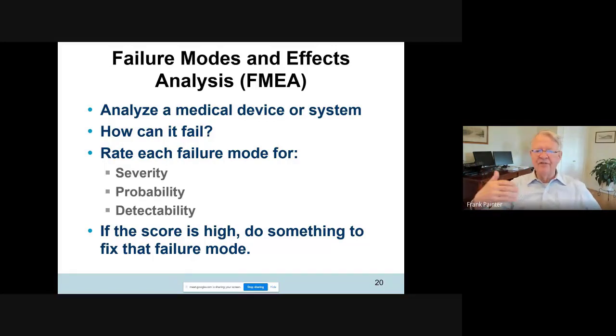So what we're going to do is have the nurses do a little check on the defibrillator every day, and they're going to plug it back in when they're done with the check. But when they start the check, they unplug it, and then they run the defibrillator. Maybe they charge it up and discharge it just to see that the batteries work. And if there's any problem, they report it immediately. And then when they're done, they plug it back in. Now, sometimes the defibrillator can be used and then rolled back to its position. And if the person doesn't know, they don't plug it back in. And then the next time they go to use it, the batteries are dead. So, it's just an example of how you might do a failure modes and effects analysis.